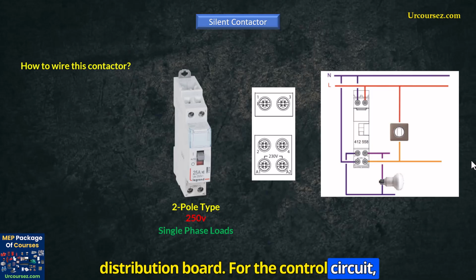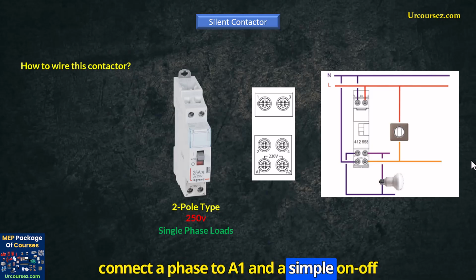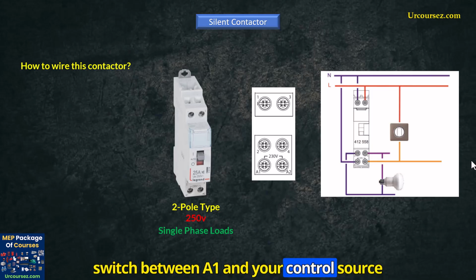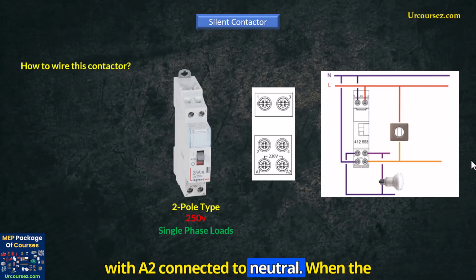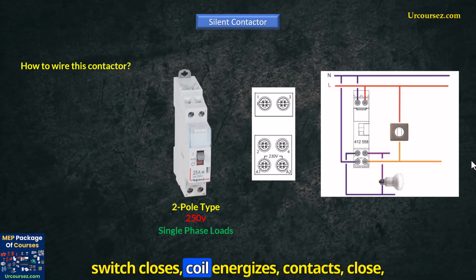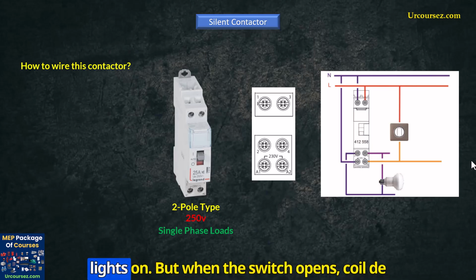For the control circuit, connect a phase to A1 and a simple on-off switch between A1 and your control source, with A2 connected to neutral. When the switch closes, coil energizes, contacts close, lights on. But when the switch opens, coil de-energizes, contacts open, lights off.